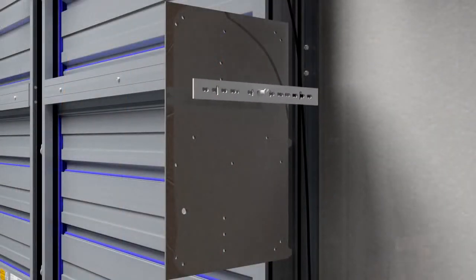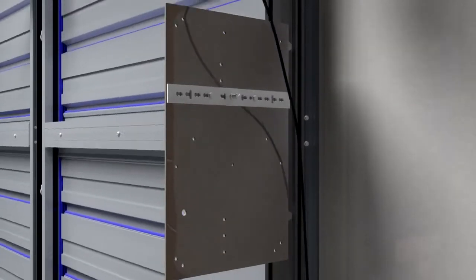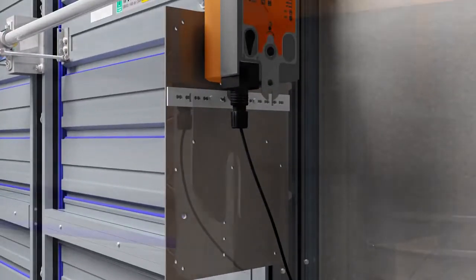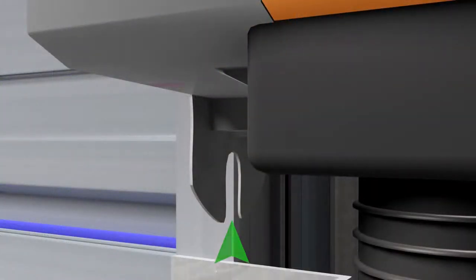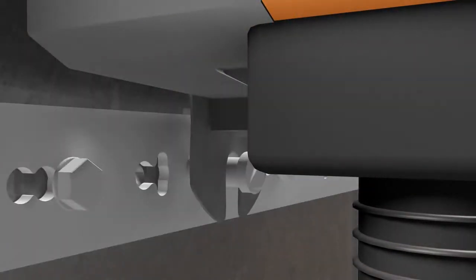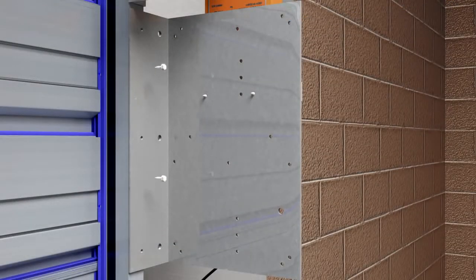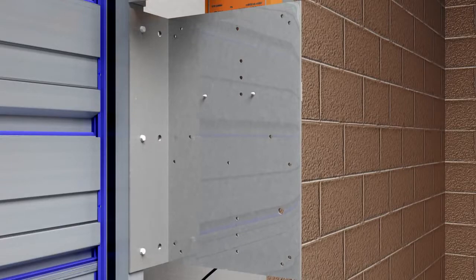Affix the anti-rotation strap to the right angle mounting bracket. Slide the mounting bracket into position so that the U-shaped slot at the base of the actuator fits over the stud of the anti-rotation strap. Use self-tapping screws to attach the mounting bracket to the damper frame.